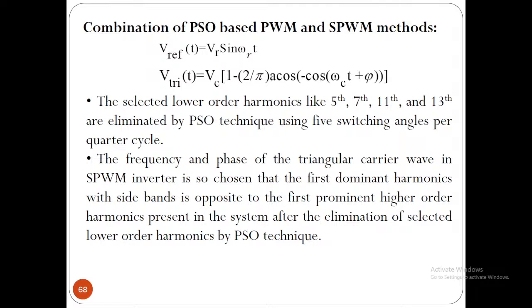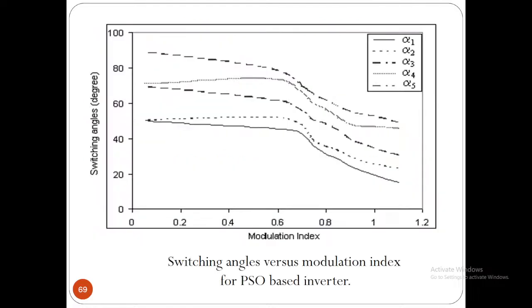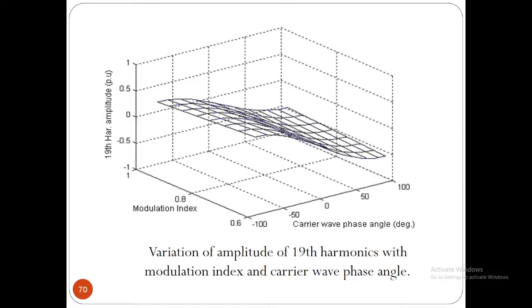Though it is in the experimental stage. Still now it is very difficult to apply, because you cannot choose this harmonics every time so that it will be opposite to the dominant one. It is very difficult. But in certain cases you can find it. So that was tested. So in that way, it is selected, almost similar to the earlier one, the 5 switching angles, eliminating the 4 harmonics. Then 19th harmonics appears. 5th, 7th, 11th, 13th, these are eliminated. So 19th is appearing after elimination of those.